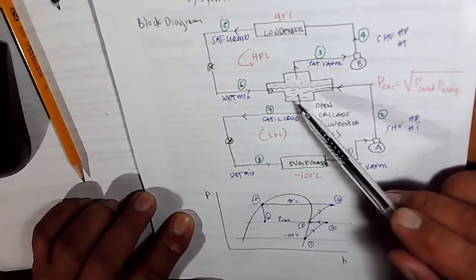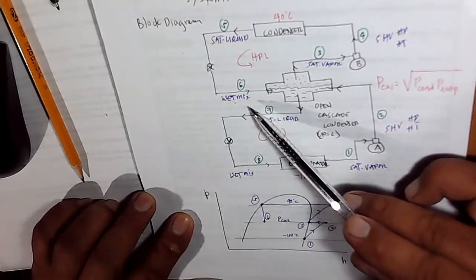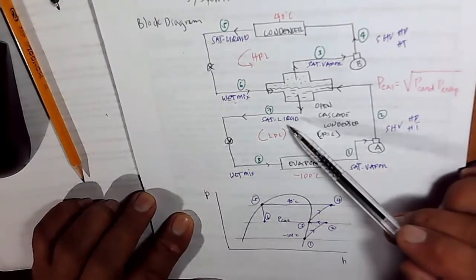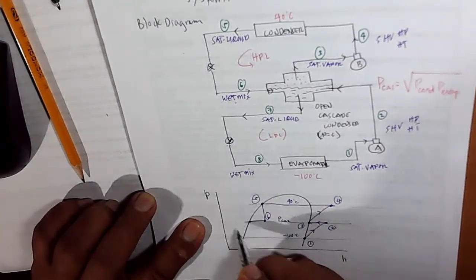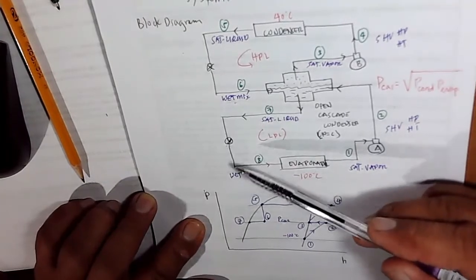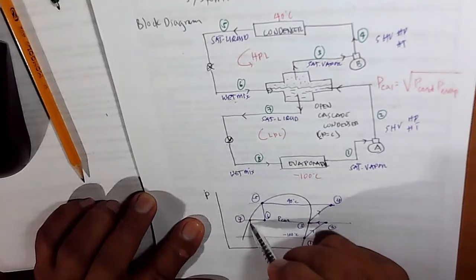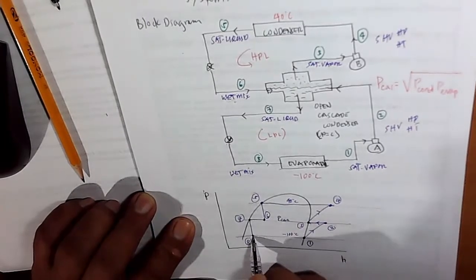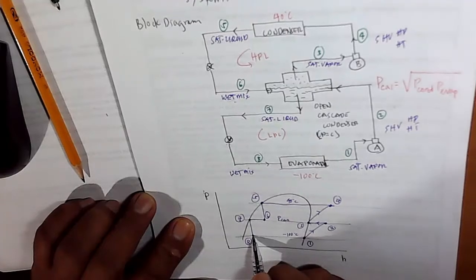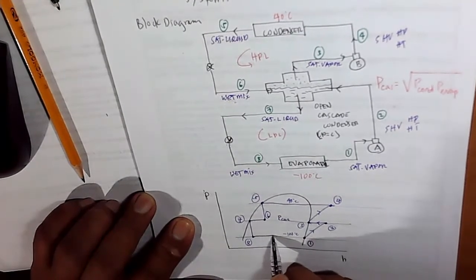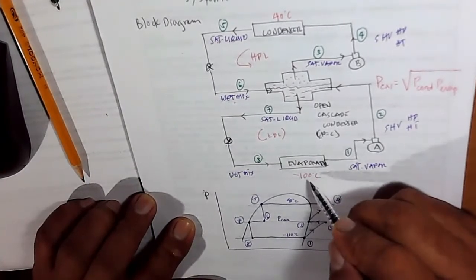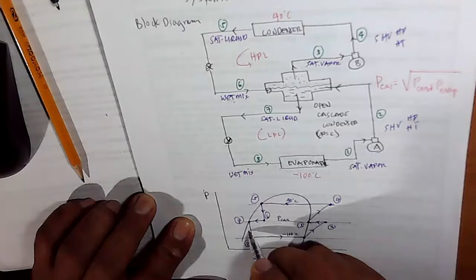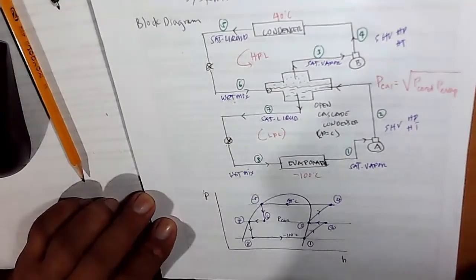It will go to your expansion device at constant enthalpy — a line going straight downward — until it crosses the pressure corresponding to your cascade condenser. This is your point 6. At point 7, as all liquids settle down, the wet mixture is converted into pure saturated liquid. Then for the next expansion device, across constant enthalpy once again, going straight down until you cross the pressure corresponding to negative 100 degrees Celsius — this is your point 8. Going from point 8 to point 1, the wet mixture changes to saturated vapor by heat absorption from the fluid in your evaporator. That is your pH diagram of your cascade refrigeration system.